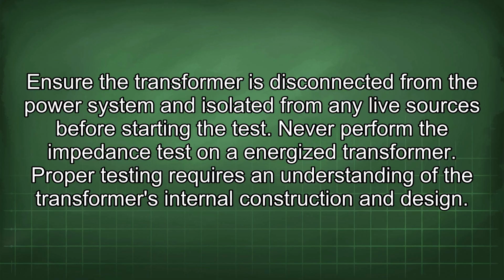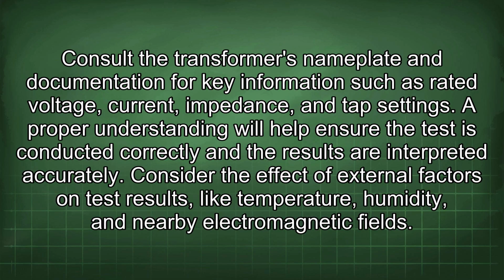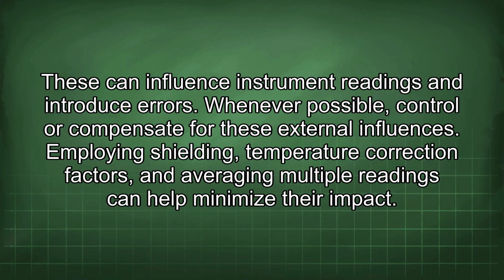Proper testing requires an understanding of the transformer's internal construction and design. Consult the transformer's nameplate and documentation for key information such as rated voltage, current, impedance, and tap settings. A proper understanding will help ensure the test is conducted correctly and the results are interpreted accurately. Consider the effect of external factors on test results, like temperature, humidity, and nearby electromagnetic fields. These can influence instrument readings and introduce errors. Wherever possible, control or compensate for these external influences. Employing shielding, temperature correction factors, and averaging multiple readings can help minimize their impact.